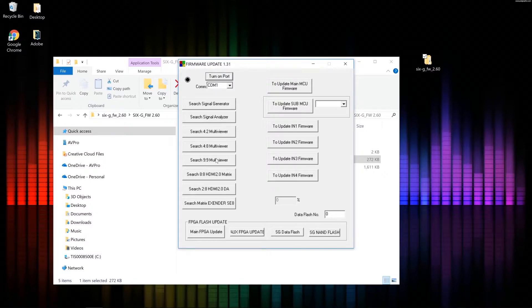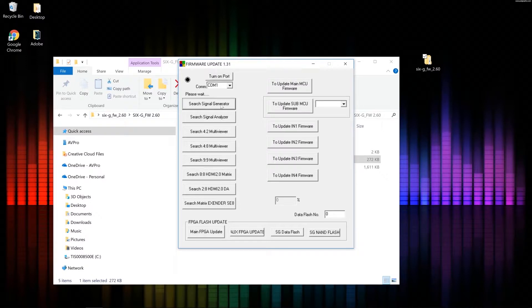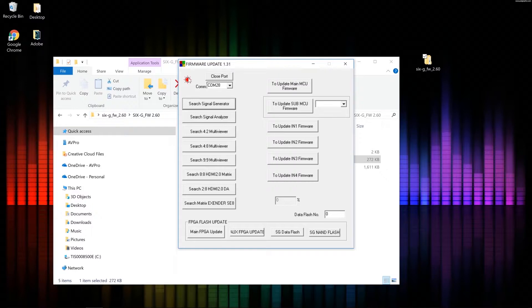And there's our firmware updater. So the first step here is to click search signal generator. Now again, my generator is plugged in via USB. So I click search signal generator. I get a red light and I have COM28. So I did get a COM port. I do have a red light. I know my 6G is connected.